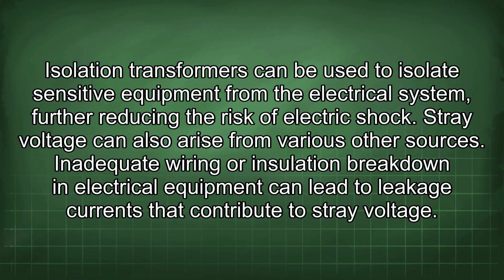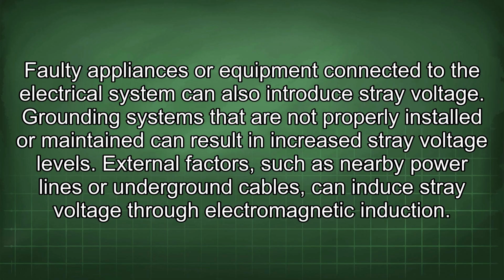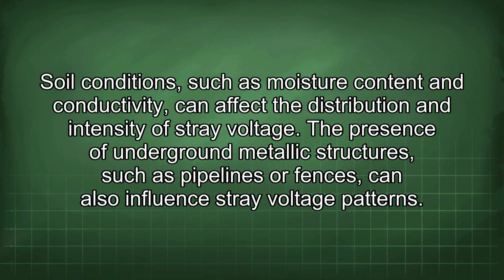Stray voltage can also arise from various other sources. Inadequate wiring or insulation breakdown in electrical equipment can lead to leakage currents that contribute to stray voltage. Faulty appliances or equipment connected to the electrical system can also introduce stray voltage. Grounding systems that are not properly installed or maintained can result in increased stray voltage levels. External factors, such as nearby power lines or underground cables, can induce stray voltage through electromagnetic induction. Soil conditions, such as moisture content and conductivity, can affect the distribution and intensity of stray voltage. The presence of underground metallic structures, such as pipelines or fences, can also influence stray voltage patterns.